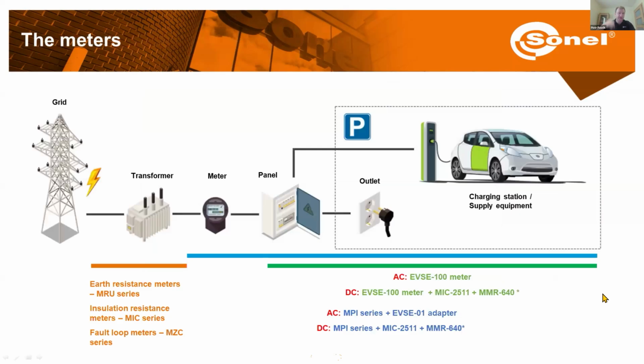Okay, so now let's look a little bit at the test equipment. That's what we do at Sonel. Here I would recommend the EVSE-100 meter. That's a standalone meter designed to check electric vehicle charging stations and their safety. So we just need one meter. Maybe in case of DC charging stations, we might want to additionally use the MIC 2511 insulation resistance meter to check the SPDs. And a micro-ohmmeter, as it has higher test currents to check continuity. At Sonel, that's the MMR 640.